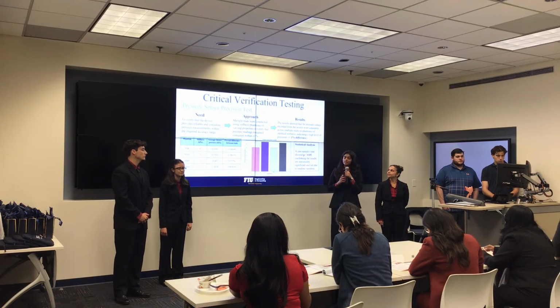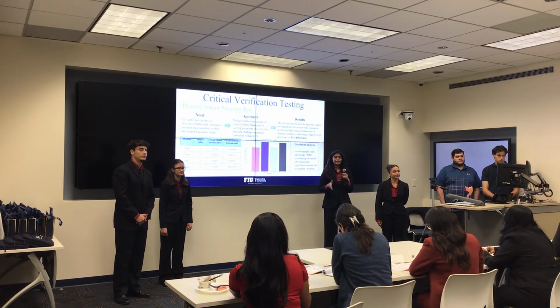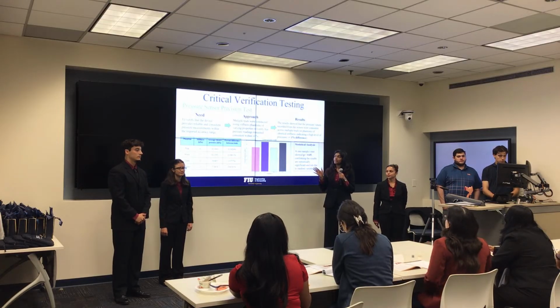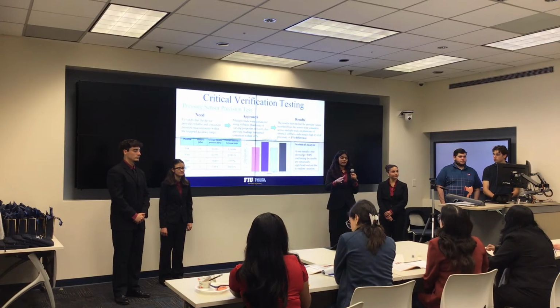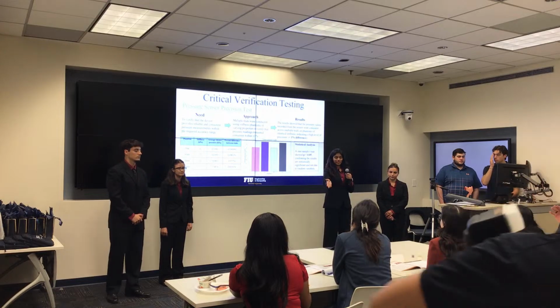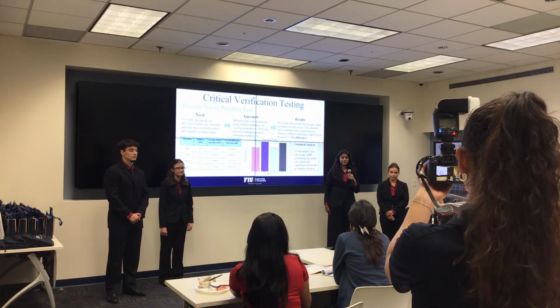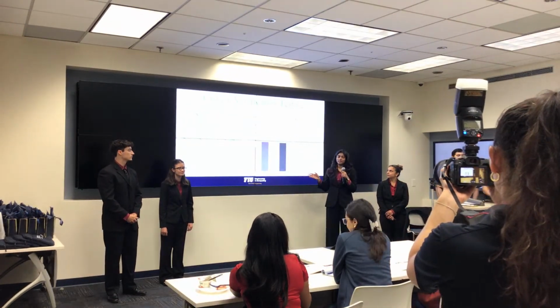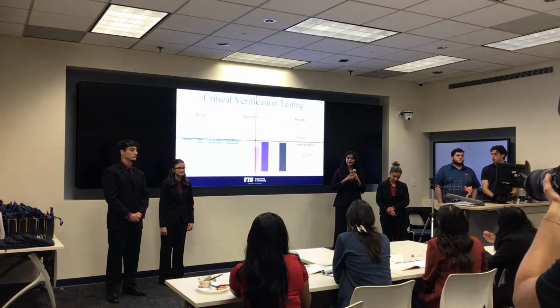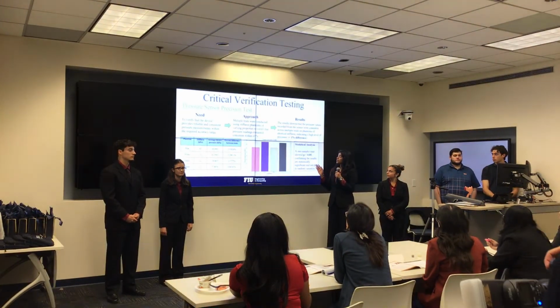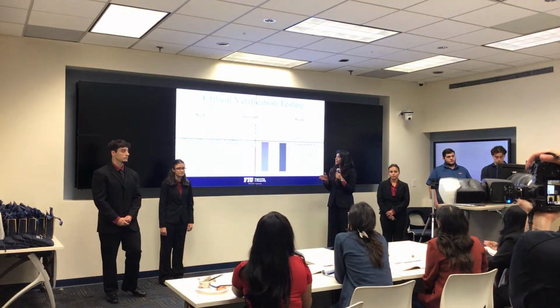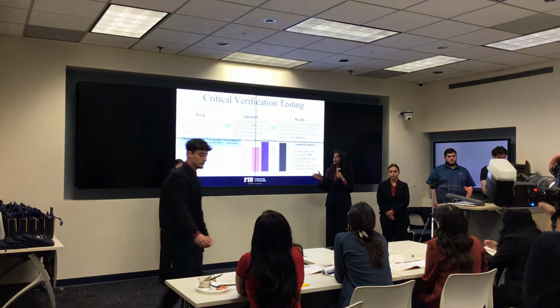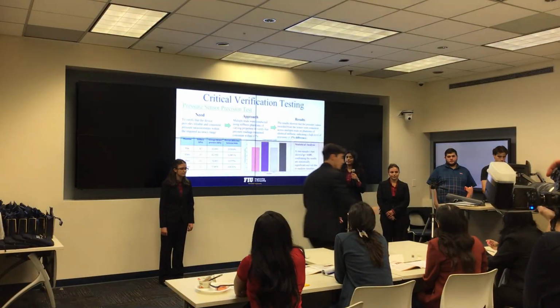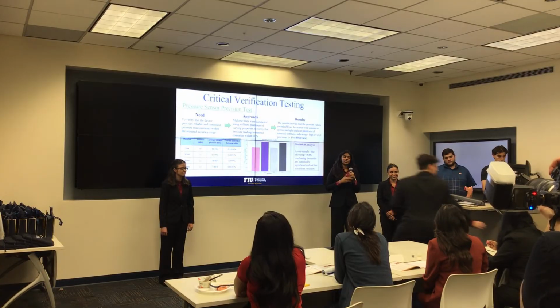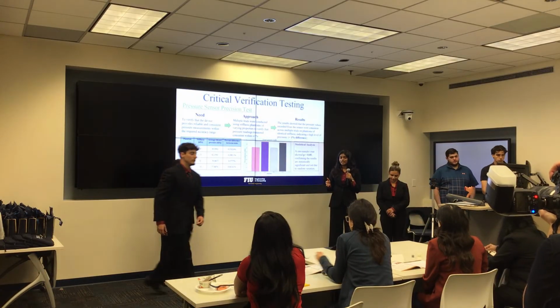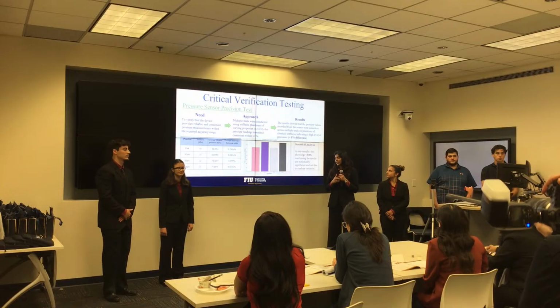The first one is the pressure sensor precision test. This is also our killer test. So what we did in this test was we placed the probe on top of the phantoms that you see on the table and collected the pressure readings accurately. So what we found out was that the device was able to give a less than 1% of variation between each of the trials of the separate phantoms, and it also gave us a p-value of less than 0.05, indicating that our results were statistically accurate.